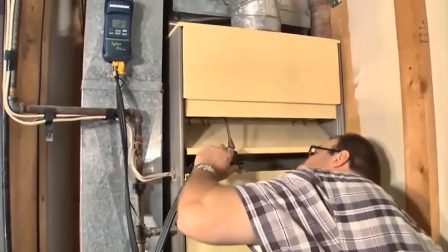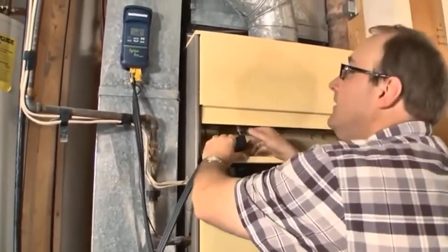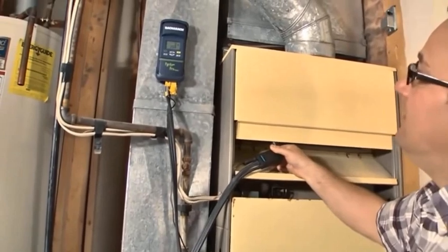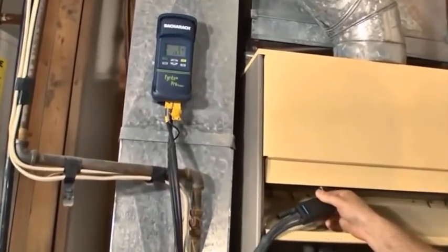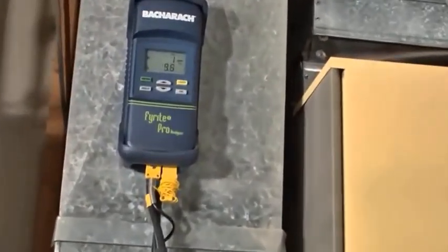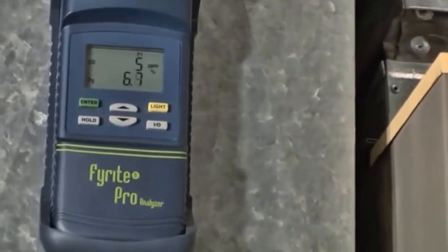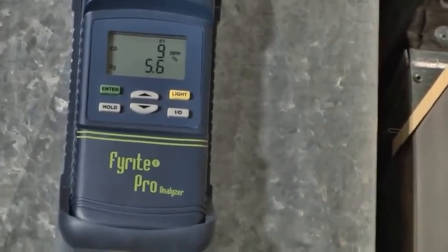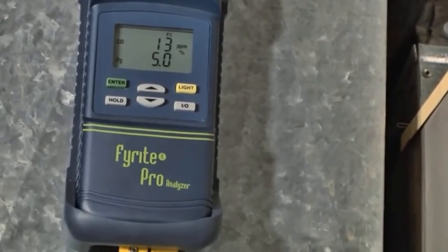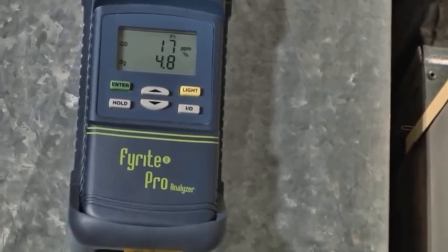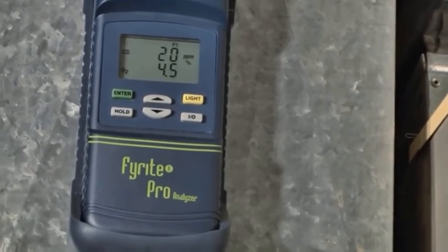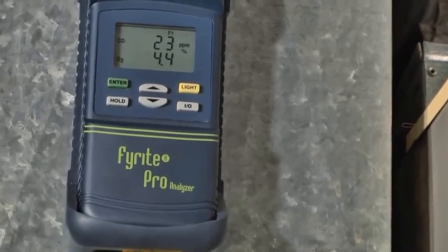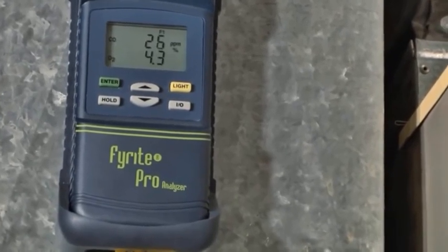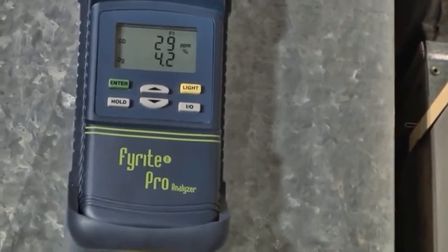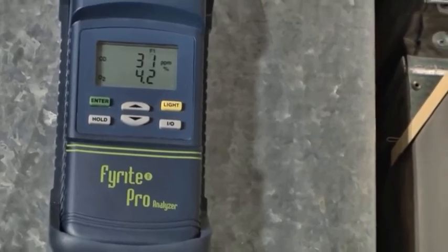So I'll stick my probe up into the first one here, and you see my oxygen starting to drop, and it's starting to read my parts per million of carbon monoxide. I always want to be under 100 parts per million. Usually on a good running furnace, you'll be well below that. We'll wait till it stabilizes, then we'll move to the next one.